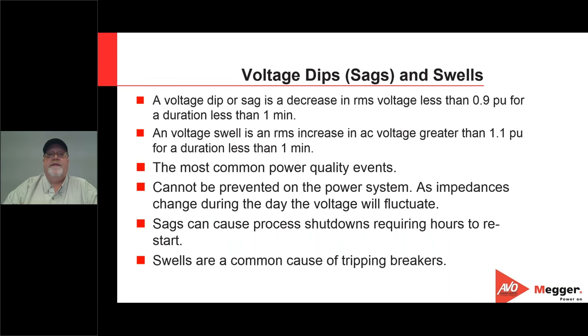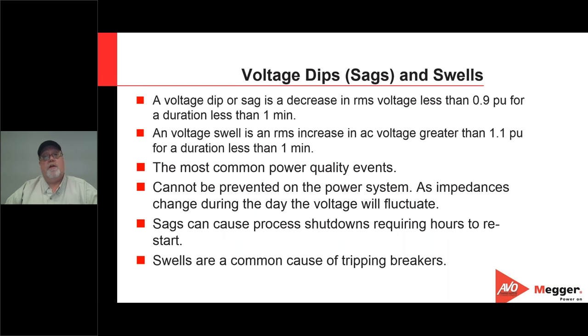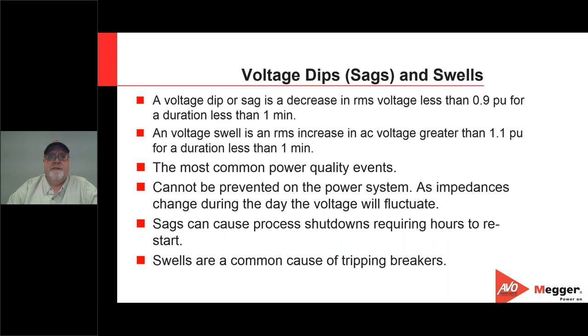A voltage swell is basically when the voltage increases to 110% or 1.1 per-unit above nominal for less than one minute. So when we look at under-voltage and over-voltage conditions, these last longer than a minute. Dips, SAGs, and swells last less than a minute. SAGs and dips are your most common power quality events — they cannot be prevented because as impedances change on your system during the day from loads being turned on and off, you're going to see them occur.